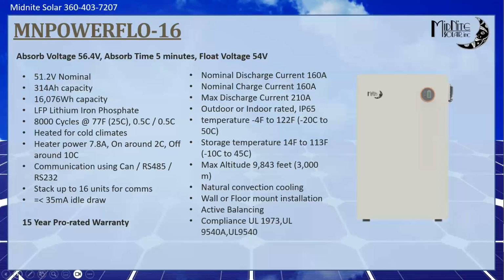Nominal discharge current of 160 amps and a nominal charge current of 160 amps. The maximum discharge is 210 amps. So we do say you can use one of these with one of our all-in-ones. Under the exact right conditions, you can overload a single battery. So again, if you're designing the system such that the customer is going to be hitting that all-in-one inverter with a 12, 14 kilowatt load now and then, you probably need more than one battery. If the customer's only got 5,000 watts of load that they may ever run, but you predominantly want to sell to the grid and have a little bit of backup, then one battery is fine.